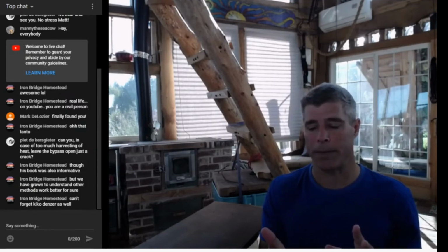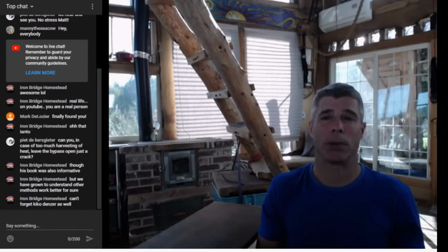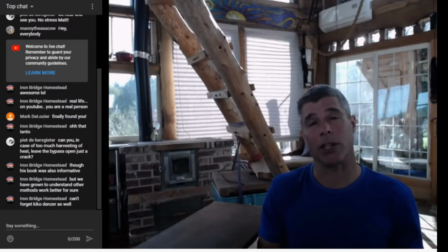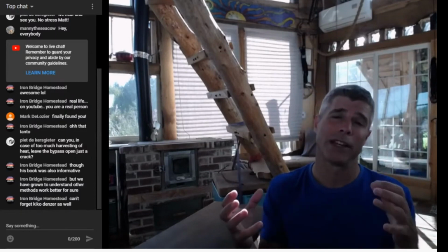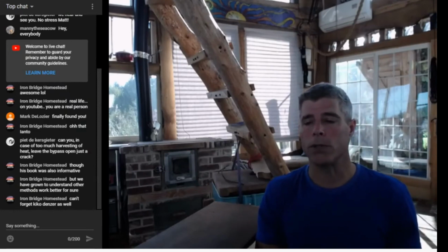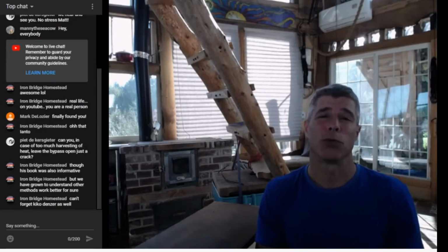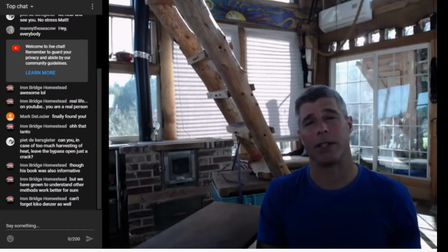Once you're in the chimney, most of us aren't going to be using Class A triple wall insulated pipe. Most of us are going to be using non-insulated pipe. And so that chimney flue pipe typically represents a pretty efficient radiator. It's cooling the gases quite quickly because it's shedding that heat into your space. So those single wall flue pipes do a really good job of removing heat from the exhaust gases, and in doing so, they really can harm your chimney's efficiency.